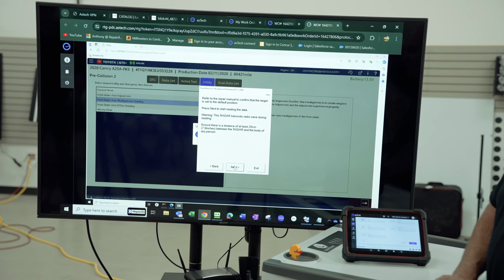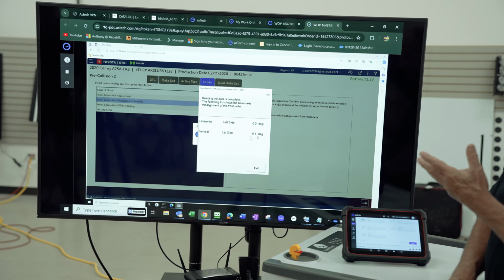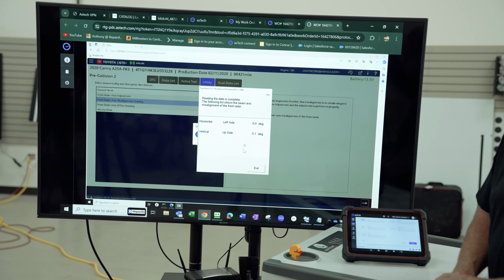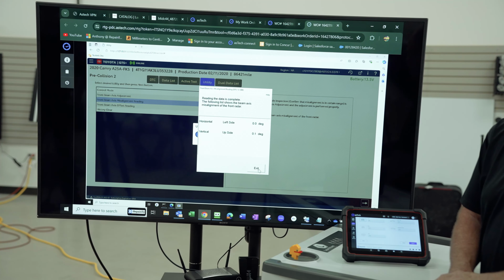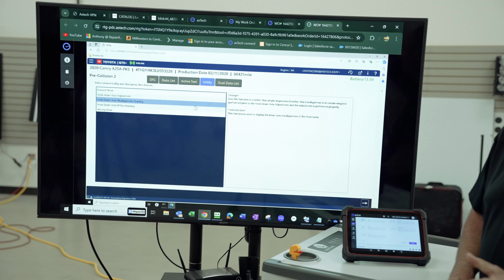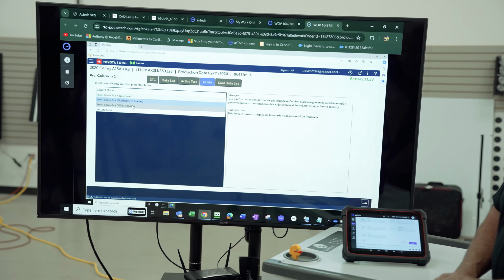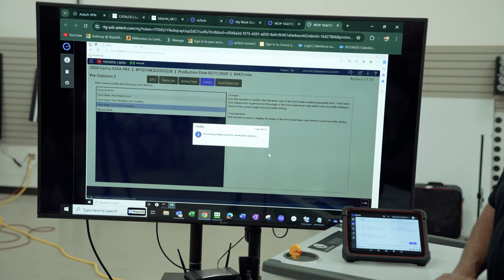And so it should read zeros is my bet. We might get a 0.1 every once in a while. It just depends on if we're kind of in between. So we've got an in-between number of 0.1, which is well within the specifications. It was within specifications, quite frankly, at 0.3. And so we're completed with this.